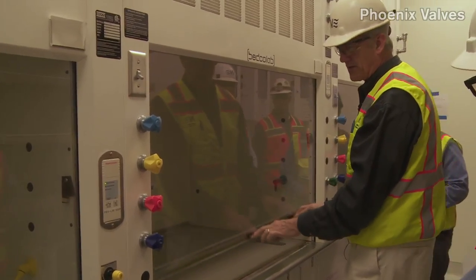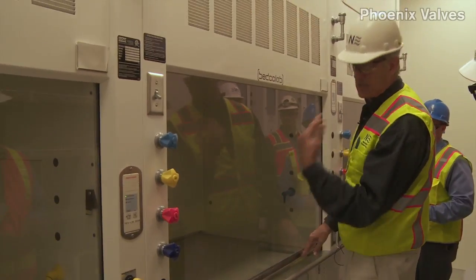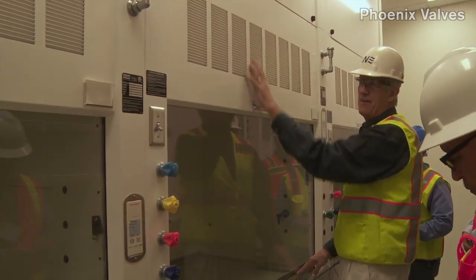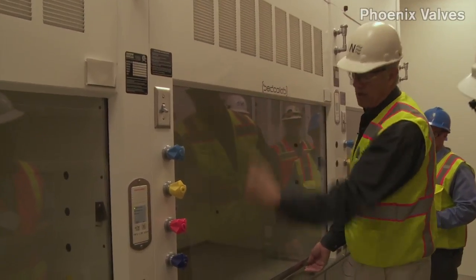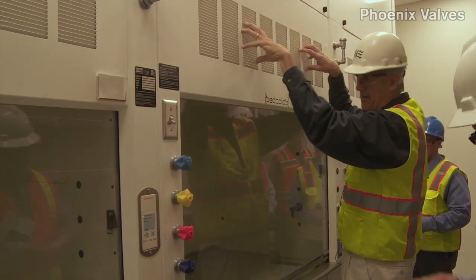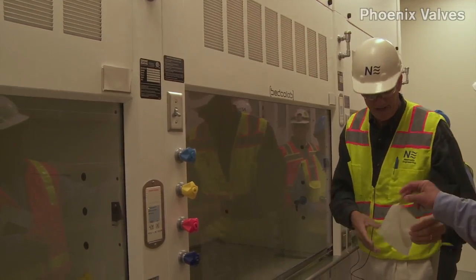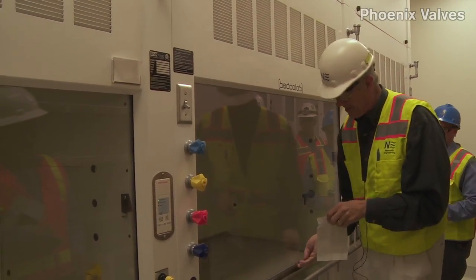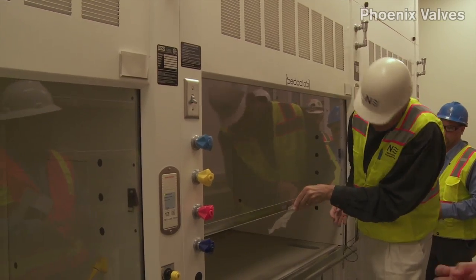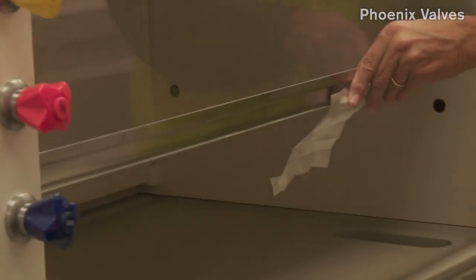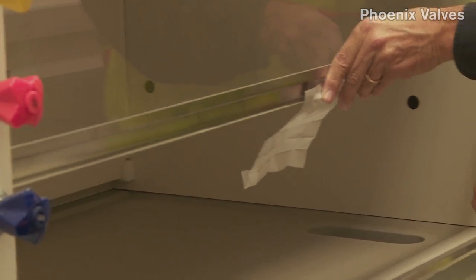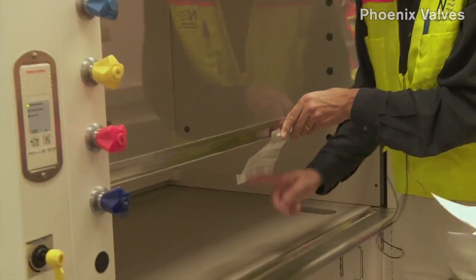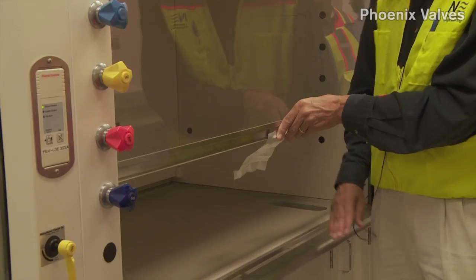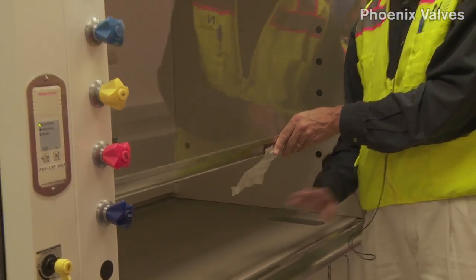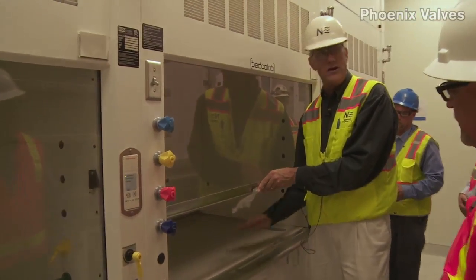You can raise and lower the sash. The flow is not changing when you raise and lower the sash. It's got a bypass up here. So when you lower the sash, air comes in over the top here into the hood. Oh, that's pretty good. That's a wet wipe, but it's pretty close. Yeah, that's about right. It's about a 40-degree angle. And they look just like this, the Kimwipes do. They don't clean your hands. Maybe that's only about a 35-degree angle. So a Kimwipe's a little bit lighter. It's not wet, but it goes in at about a 40-degree angle.